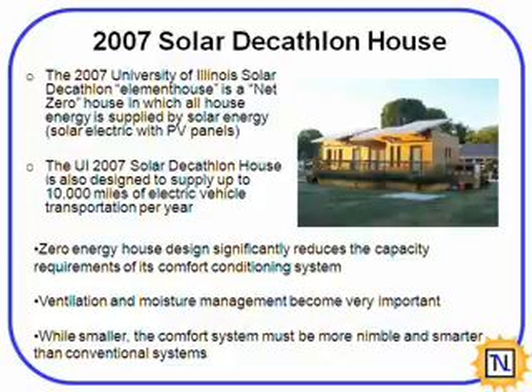Some characteristics of these types of homes then are that it significantly reduces the capacity requirements of systems. So we'll look at this more later, but these systems need to be very small. The loads on these buildings aren't very big. What's happening outside isn't necessarily being communicated to the interior space. And this makes ventilation and moisture management extremely important. And many people have found out the hard way, if you don't manage these things properly, you're going to see mold, mildew, condensation on the inside of your house. So this is one of the main differences and an important point.